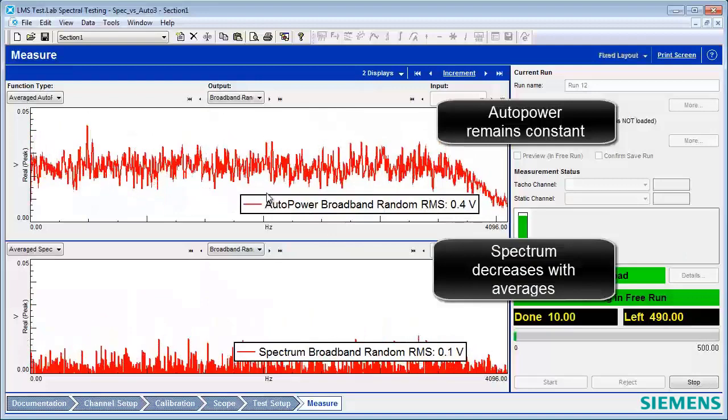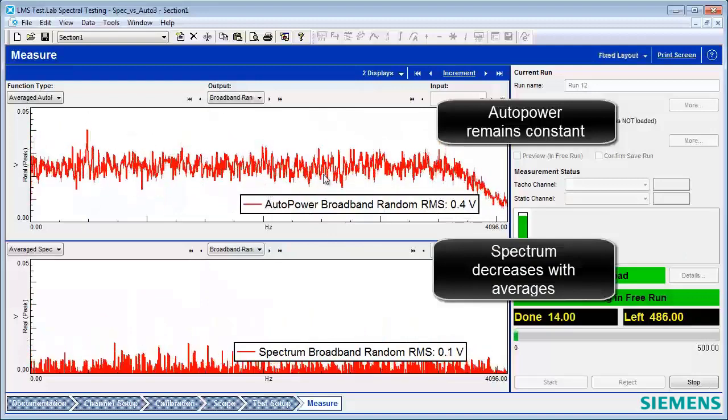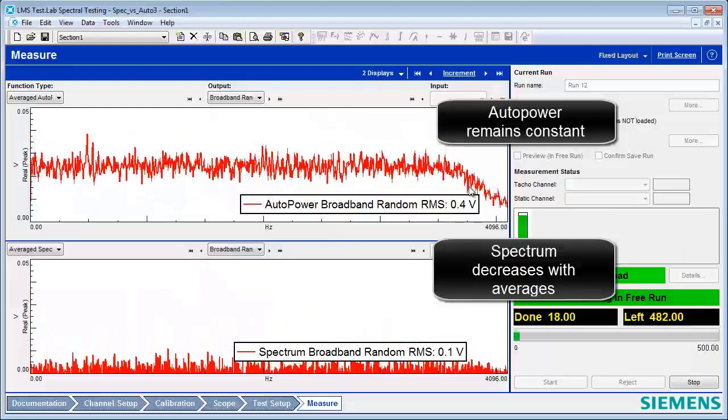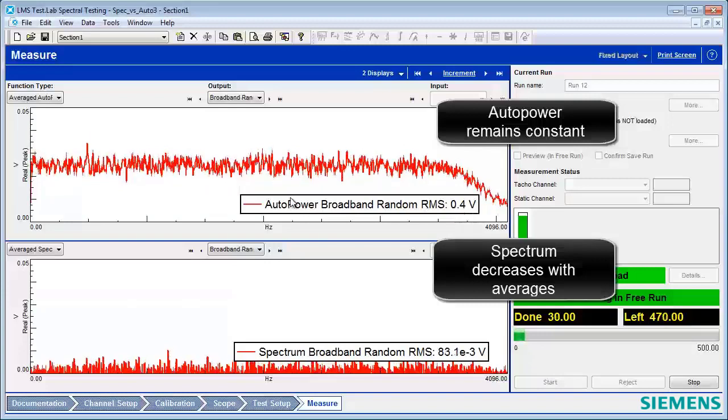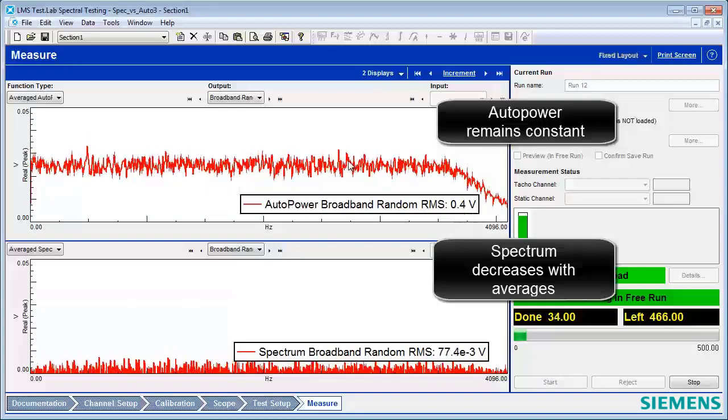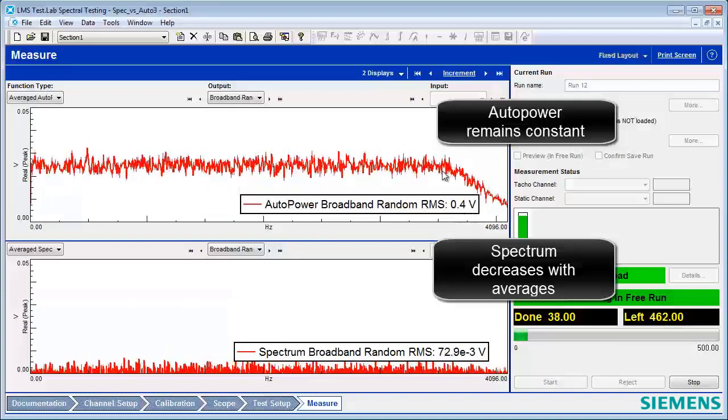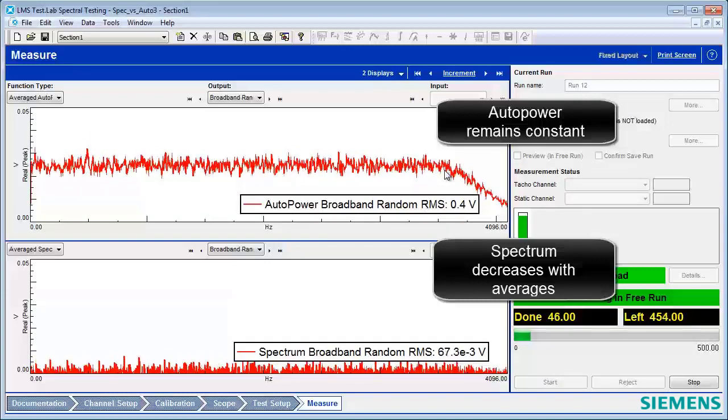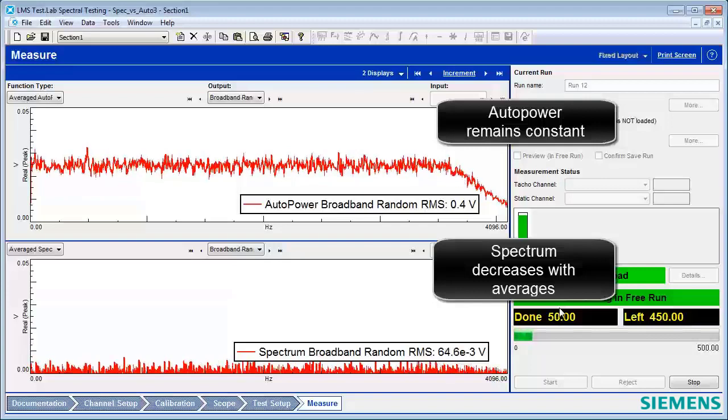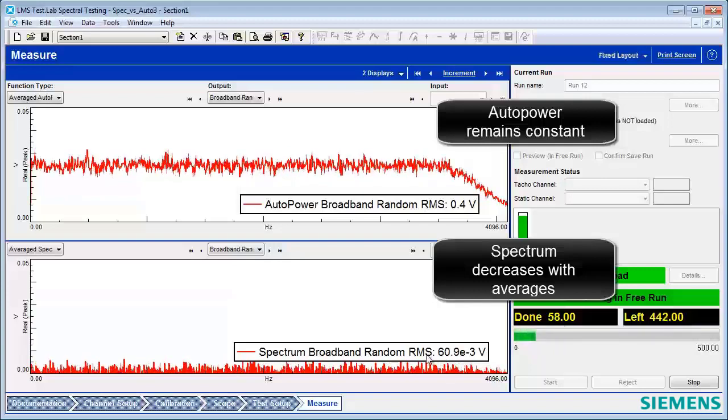And we can see that the auto power remains a constant 0.4 volt RMS and stays at the same amplitude even as the number of averages increase.